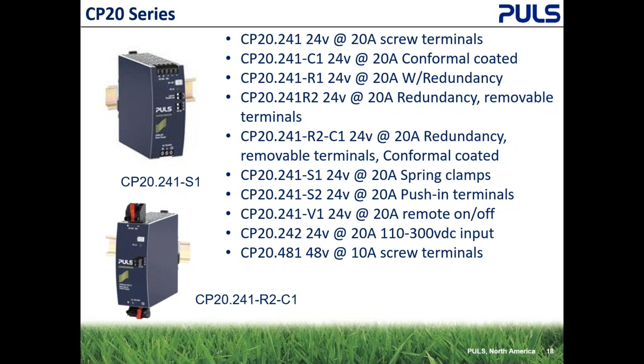CP20 available in different configurations. The bottom we have 48 volt. The third one up is a V1, which is something new. V1 is a remote on off. So the input stays on. It turns the output on and off by giving it a 24 volt signal. Somebody must have asked for this. That's why we have it. Second up from the bottom, we take 110 to 300 volt DC and supply 20 amp output.